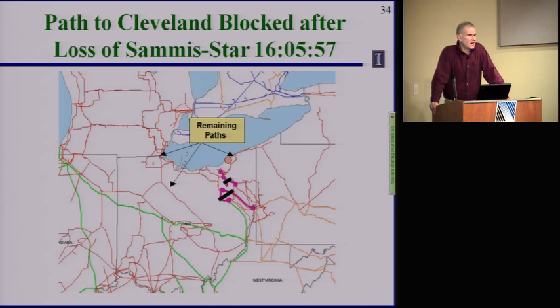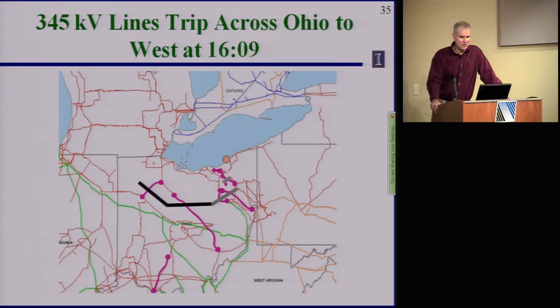We've been mostly focusing on Northeast Ohio. The black lines there show the lines that tripped. We've got 3 of the paths tripped there into Ohio. Actually, I think all 4 of them were tripped at that point. So now the Cleveland area was hanging on by paths coming in from the east along Lake Erie, and then from the rest of Ohio, they're kind of on the western part of the state. Well, one of those starts to trip. So now you get lines tripping about 4 minutes later. We lost the supply into the Cleveland area from the south west.